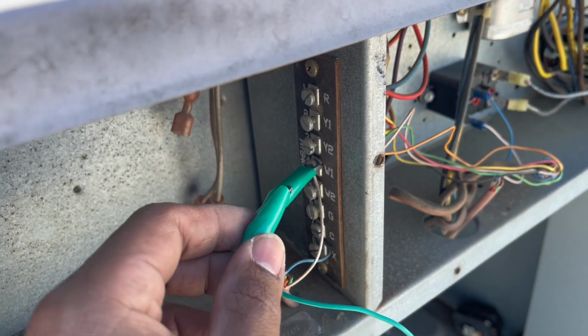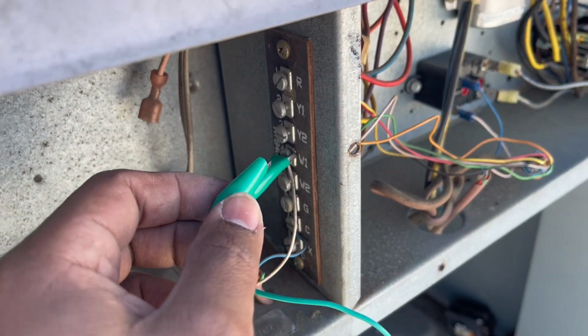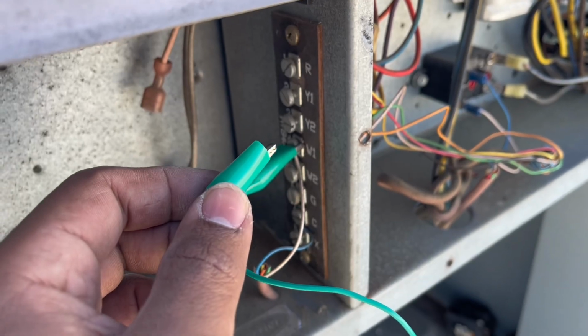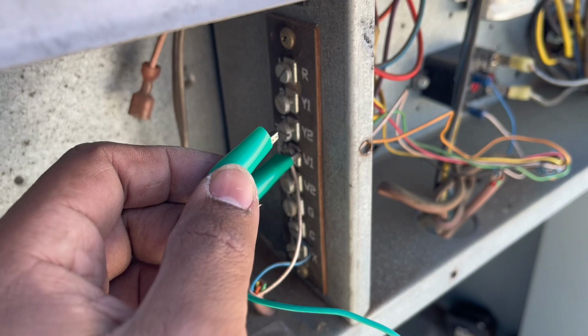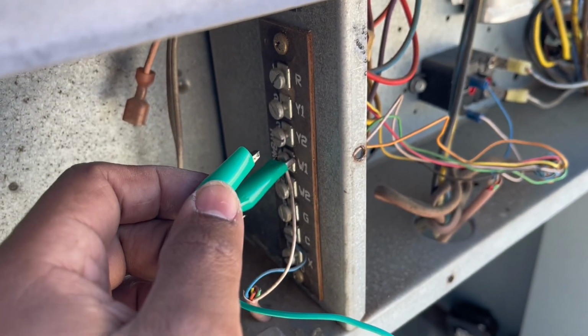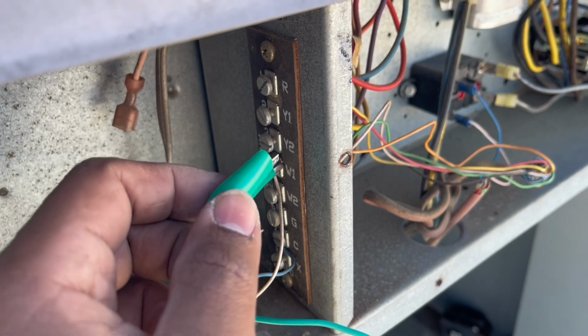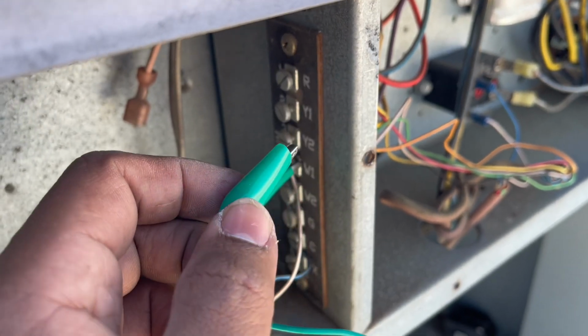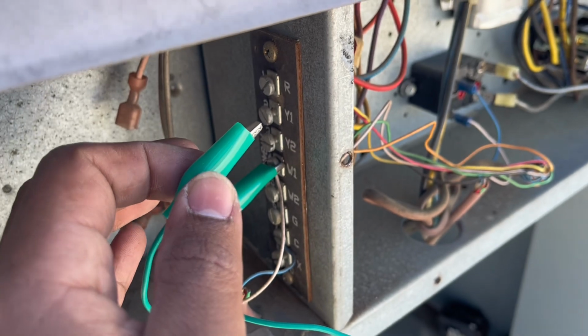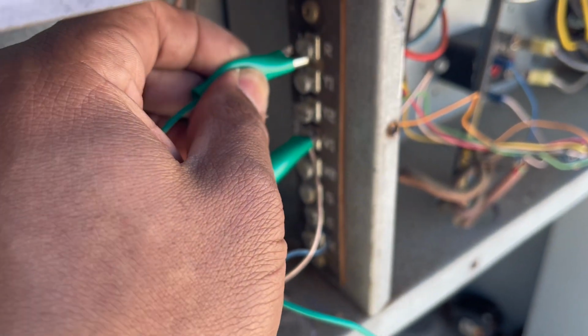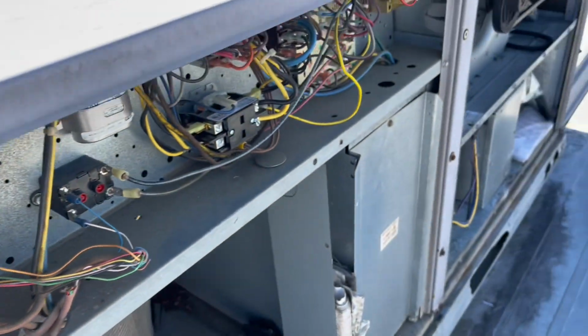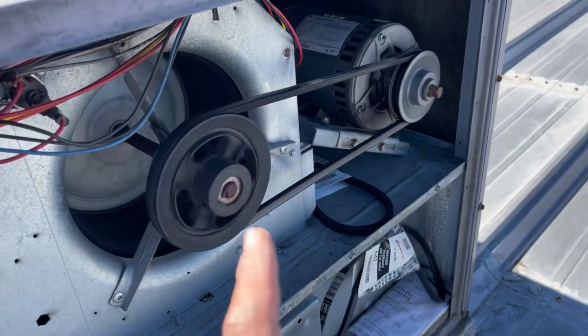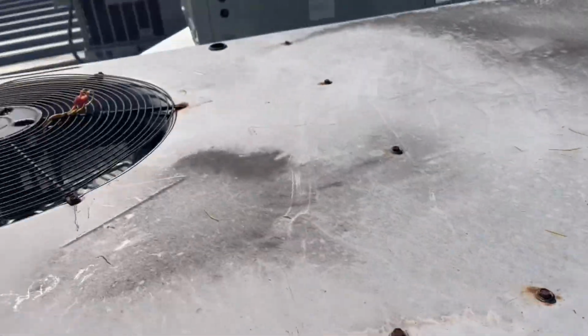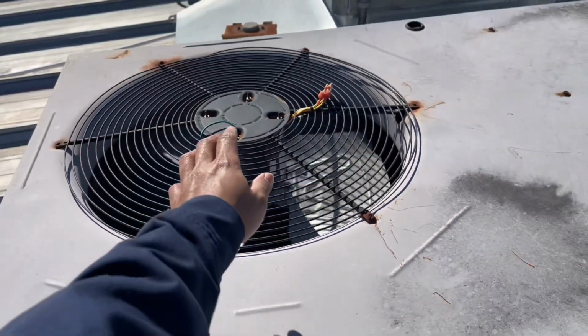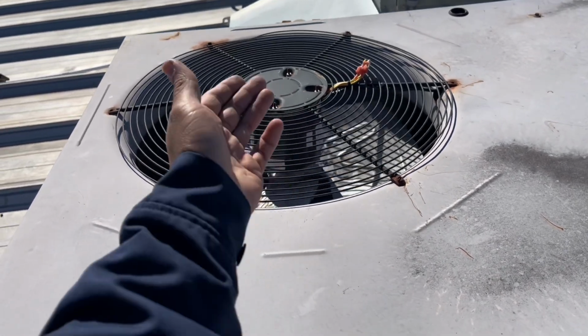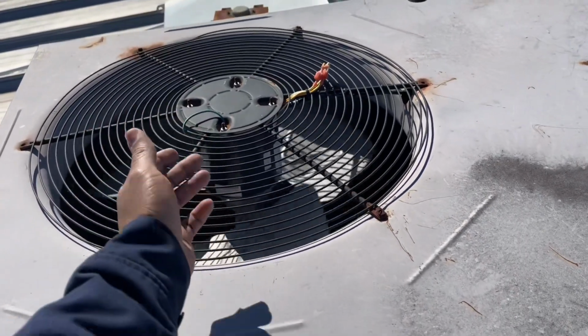So now, just to try the unit, we can connect W1, in this case for this Carrier unit. It's an old school unit, so W1 is the one that controls the heat mode with the reversing valve de-energized, but the compressor is going to be on and the fan is going to be on, I mean the blower. So we want to make sure that all that works fine. So I'm going to energize. You see that the blower is working now. The fan is working. It seems to be slow, but it's spinning really fast. And the compressor is working as well.